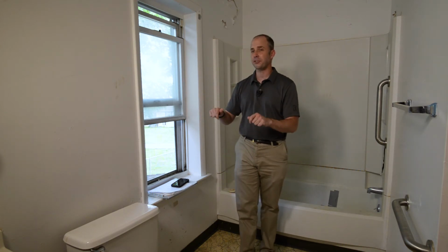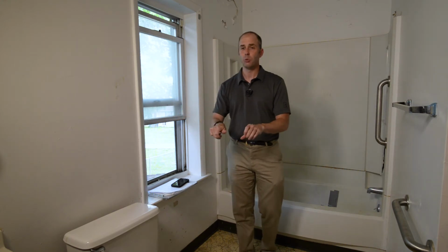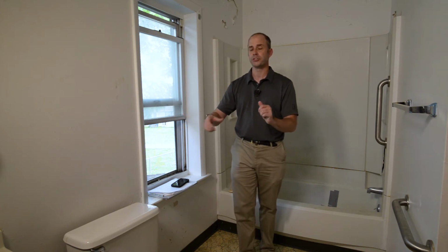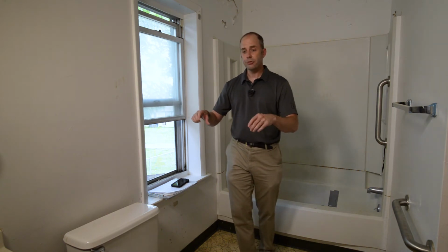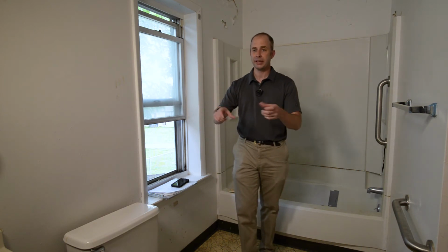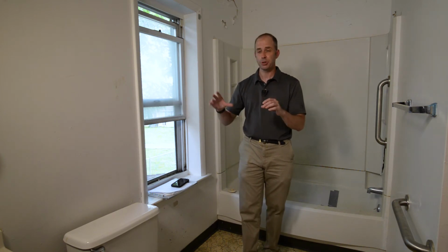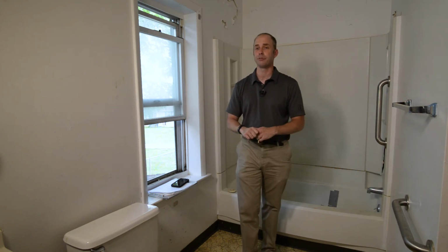So a lot of times when you see an inspector come into the bathroom, they'll turn on the faucets and they'll be letting the water run. We're letting the hot water get into the system. Granted, we turn on the hot and cold. We'll turn off the cold first to be able to check to make sure we're getting hot water inside the fixtures. Like I said about the valves, the reason why we're checking those and turning them on is that we want to make sure the valves work, that they actually stop, that they can open and close the supply lines for the fixture, and that there's adequate water pressure for each of these fixtures, because we don't want a little trickle coming out of that. How is someone going to fill a sink or a tub if we've got a little trickle coming out of the faucet itself? So it needs to be of adequate pressure.